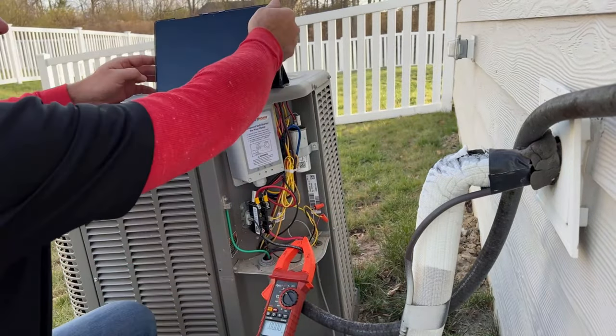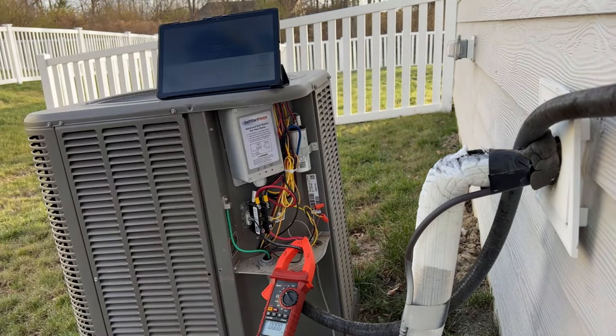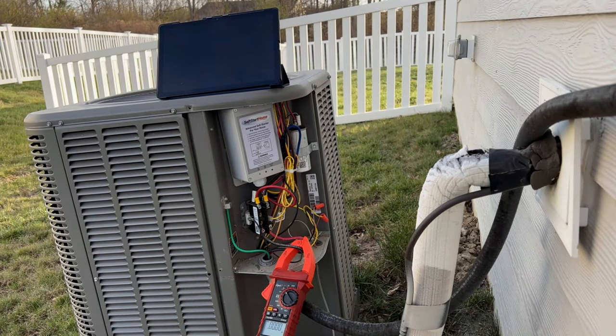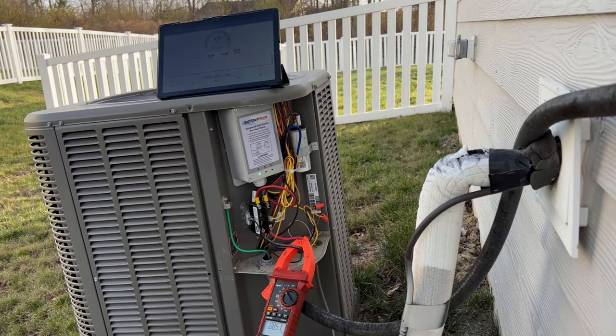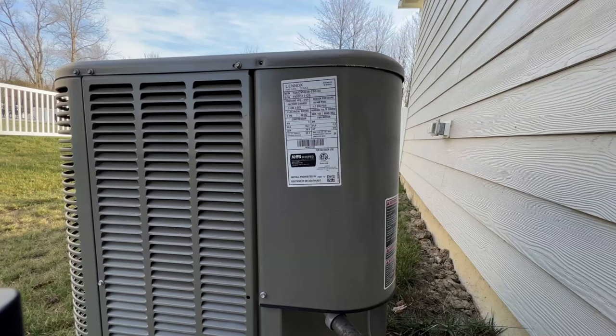Now let's fire this puppy up and see what we have as far as a difference. The soft start does give a slight delay to the compressor after the condenser fan motor, and a noticeable change in the tone of the starting of the compressor.